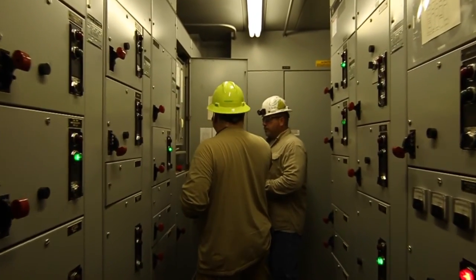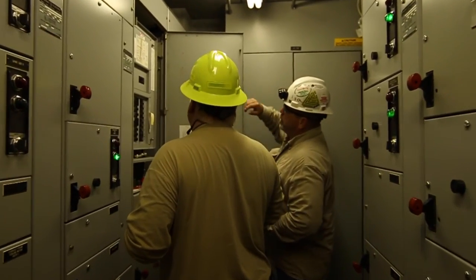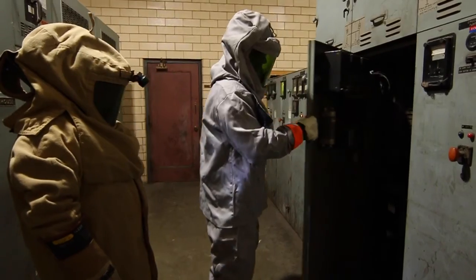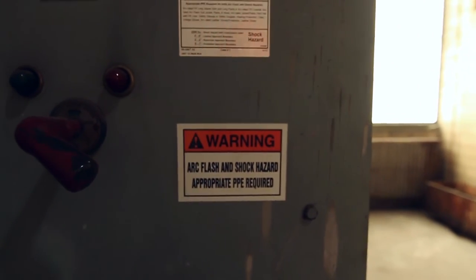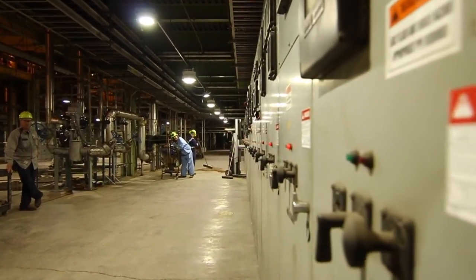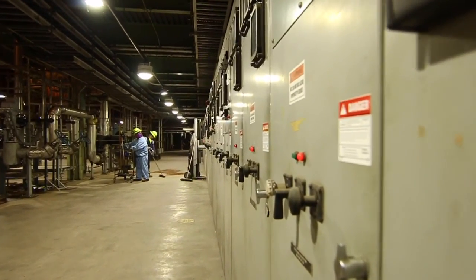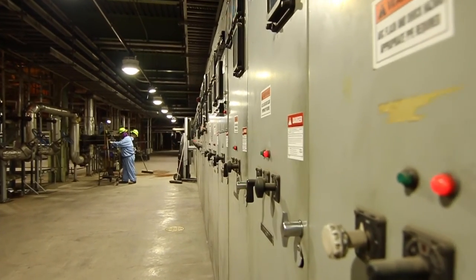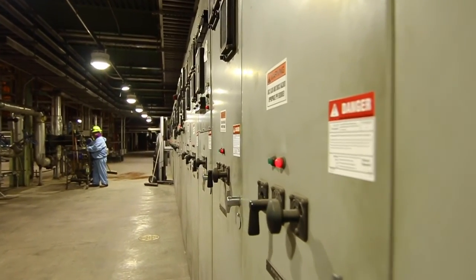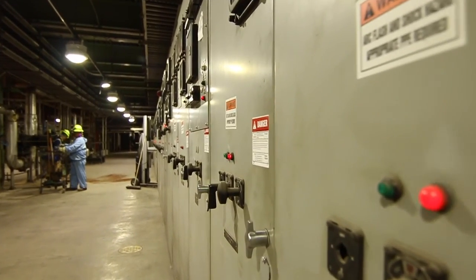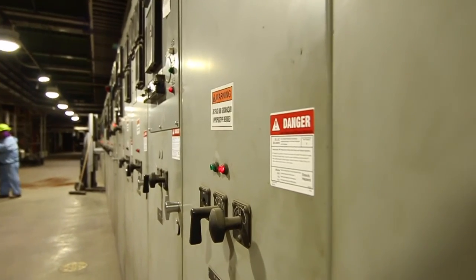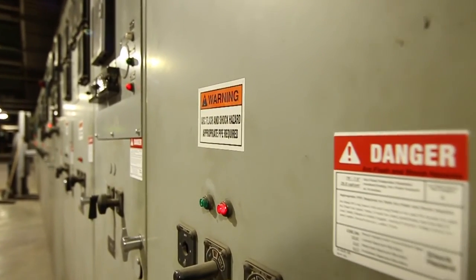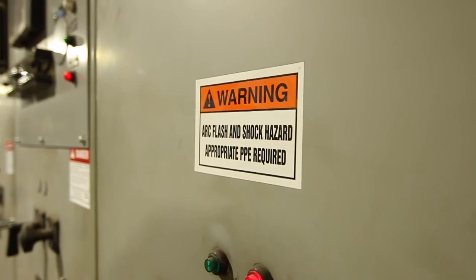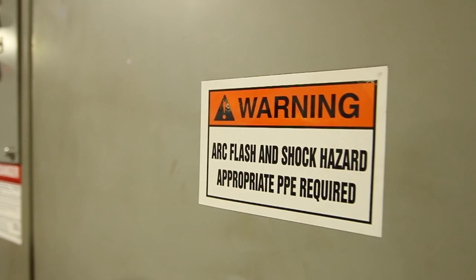Contractors performing electrical work shall ensure that their employees are provided with and properly use personal protective equipment to ensure protection from shock and arc flash hazards. When performing work where there may be exposure to live electrical components, barricades shall be used in conjunction with warning signs to prevent or limit access to work areas containing live parts. Barricades shall be placed no closer than the flash protection boundary, which is at least 4 feet from live parts unless the equipment is labeled otherwise. However, contractors shall comply with the posted calculated distance for the flash protection boundary.